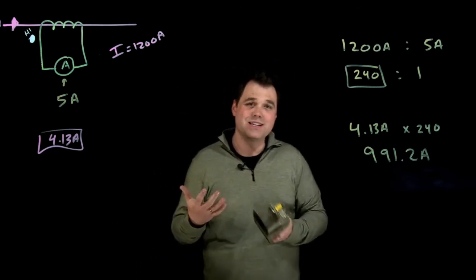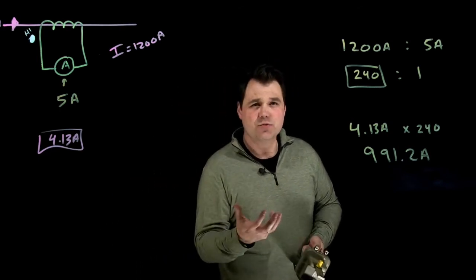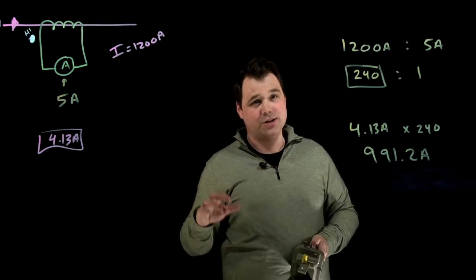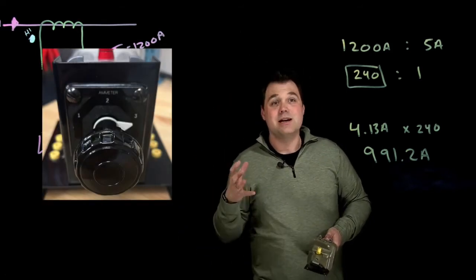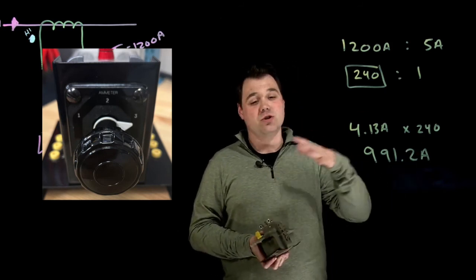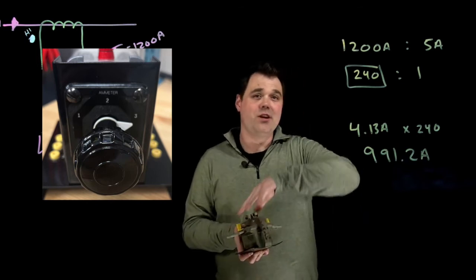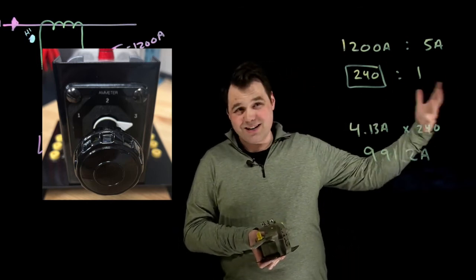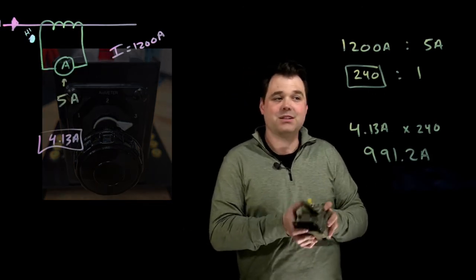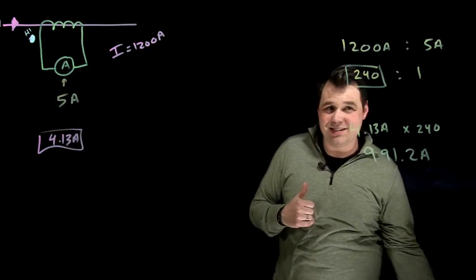What you'll also see is that a transfer switch used to switch between CTs for one single ammeter, transfer switch looking something like this, they will actually be a make-before-break set of contacts. So they're going to short circuit a CT before they close on another CT. So before they open that CT out of the circuit, they're actually going to close. That's something to keep in mind different about CTs.